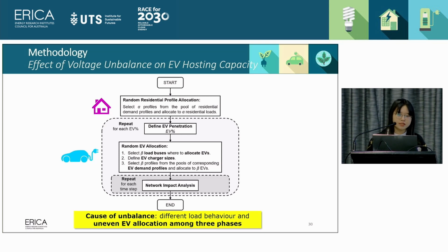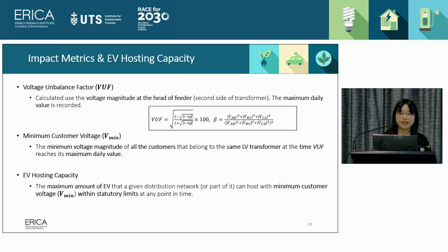So here I simulate the cause of unbalance, that is, different load behavior and potential uneven EV allocation among the three phases. So now, the impact metrics and EV hosting capacity. For the unbalance, I'm using the voltage unbalance factor. It is calculated using the voltage magnitude at the head of the feeder, and here the daily maximum value is used. The other metric is the minimum customer voltage, which is related to EV hosting capacity. The minimum customer voltage is the minimum voltage of all the customers that belong to the same LV transformer. Here it is the value at the time that the voltage unbalance factor reaches its maximum daily value.